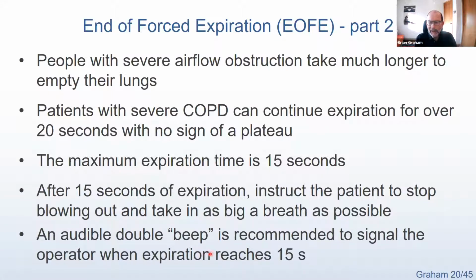Now here we've said we should have a double beep at 15 seconds to signal the operator when the expiration reaches 15 seconds. And especially for a long blow like this, that's where you're at risk of things like a bit of syncope. Patients start to get faint. You really need to be watching that patient really closely and not watching the screen trying to figure out if it's been 15 seconds. So that's why we've got that hint in there.